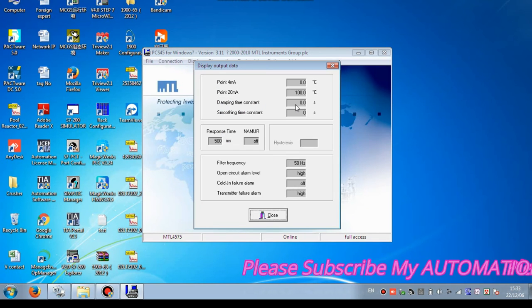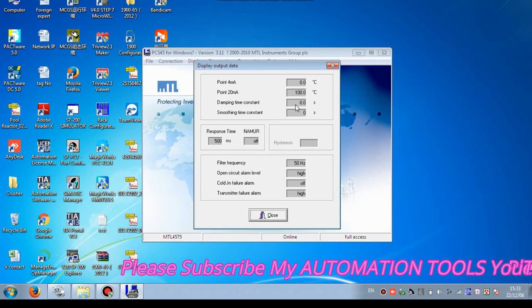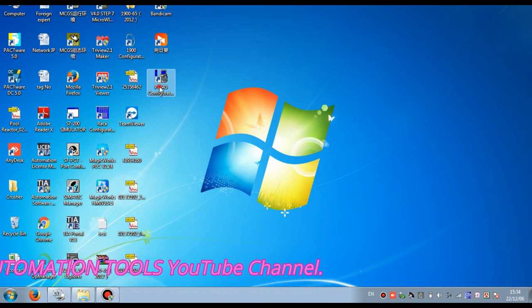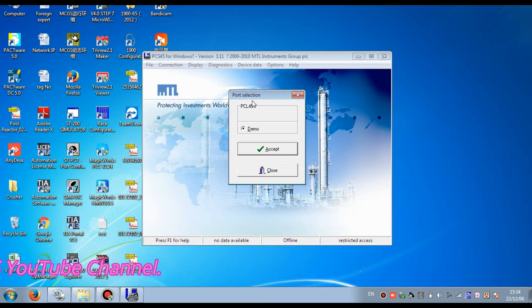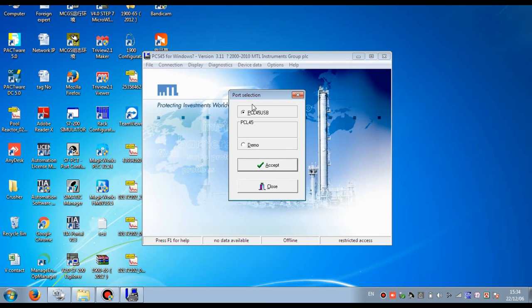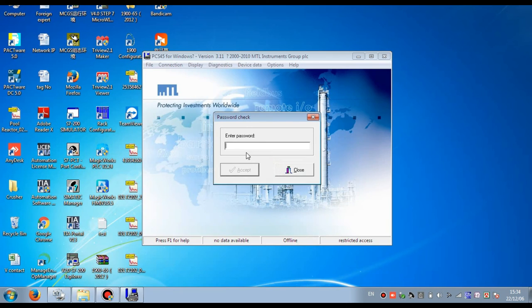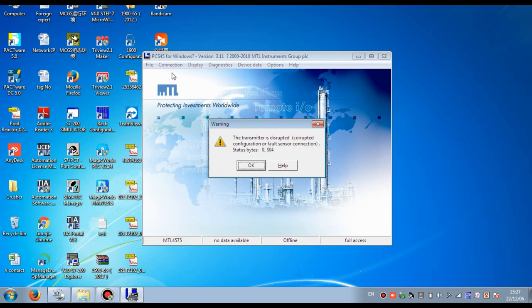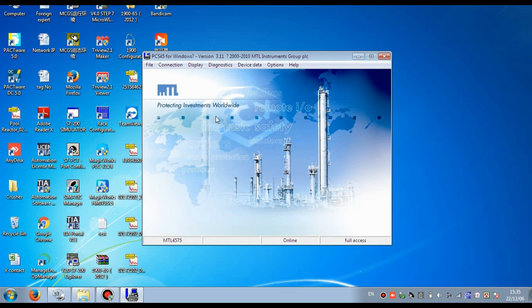We have correctly configured the safety barrier. Now I will show you the status of this MTL when we first connected it to the laptop. We open the configuration software again — here you see the adapter. Press the adapter correctly, then press Accept, enter the password 'MTL', then press Accept. You can see that now it connects directly to the safety barrier without any error. But before configuring, it was showing an alarm — this alarm was showing when we first connected the MTL to the PC. That means we have correctly configured the safety barrier MTL 4575 or 5575.